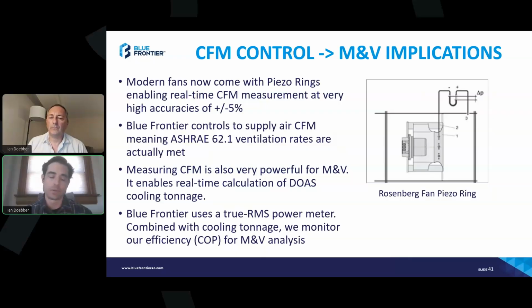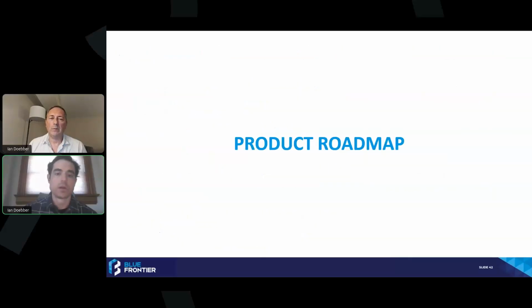From an M&V perspective, that is extremely fantastic because you can monitor not only the airflow, but if you're measuring the inlet and outlet conditions of the air, you can quantify capacity in real time. We also monitor power on our unit. So by knowing the capacity in real time and the power draw, we know real-time COP or MRE or whatever your efficiency metric is, which has been fantastic from a monitoring perspective.